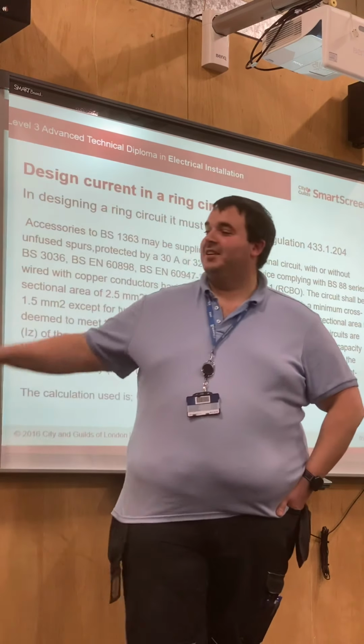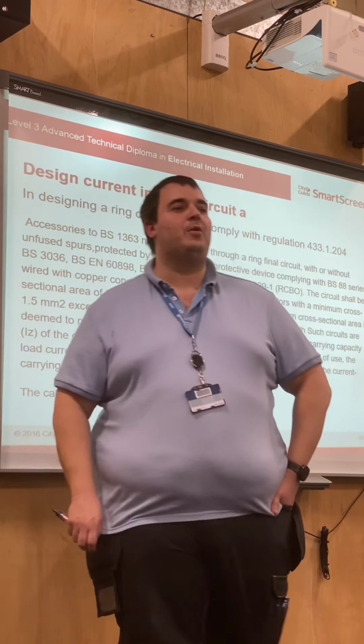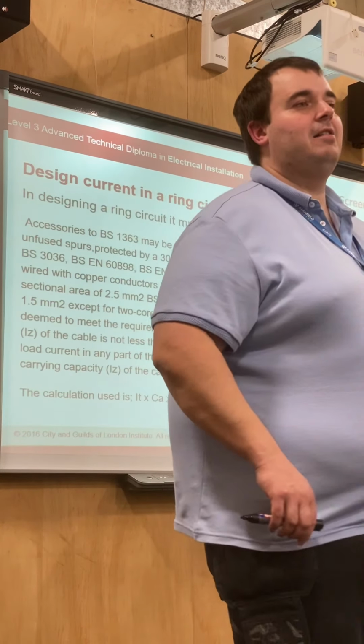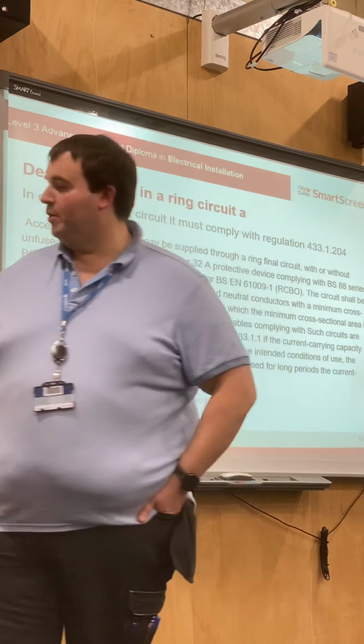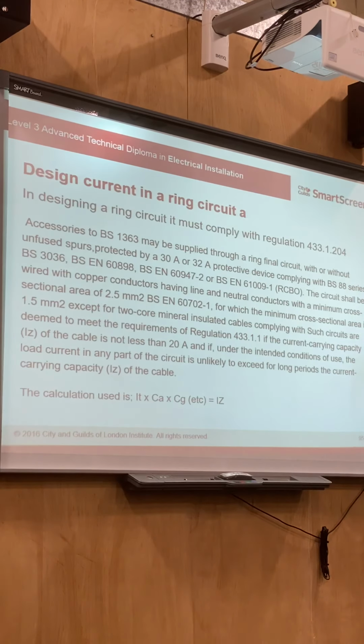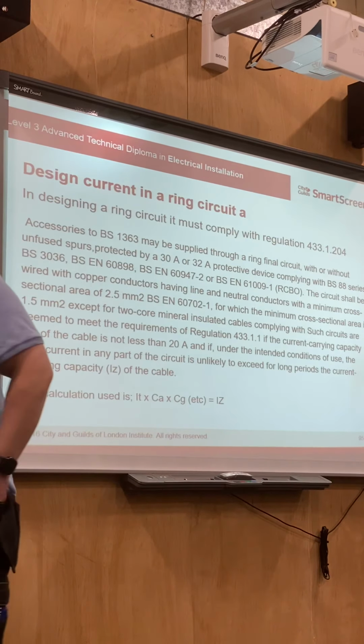Yeah. So, 2.5mm and 1.5mm earthing conductor. What is my milliohms per metre on that? On that table? 19.51. Now there are some correction tables for this. Okay.